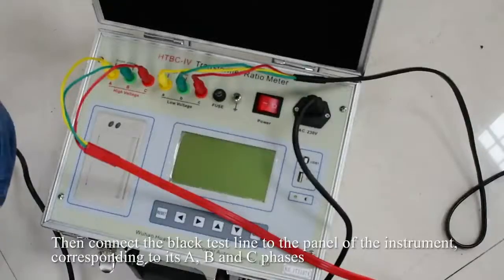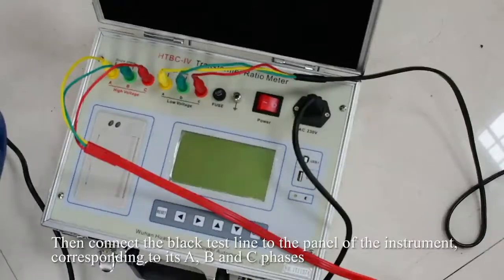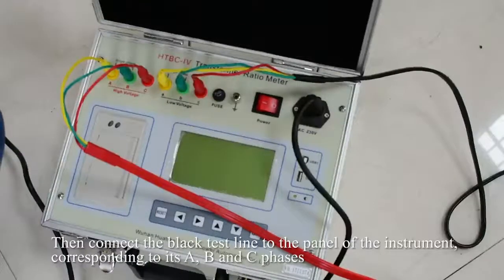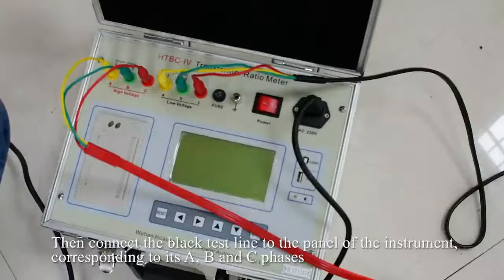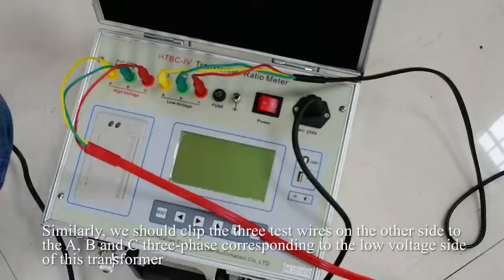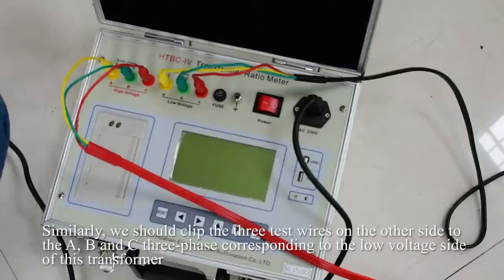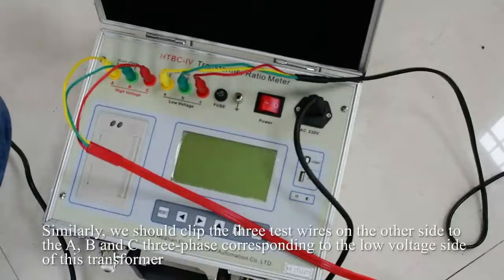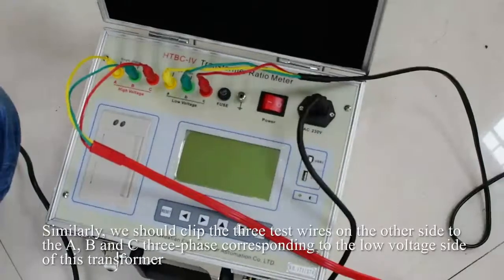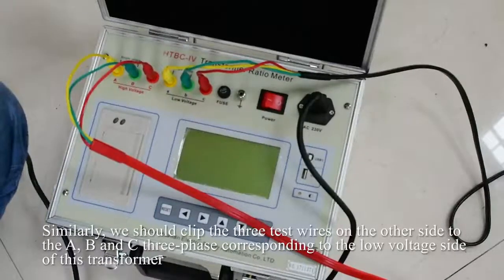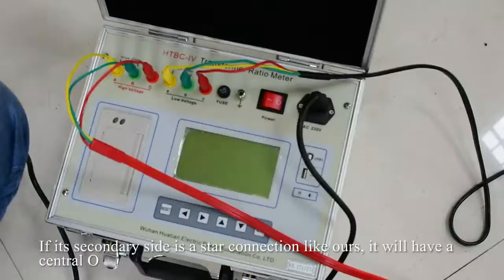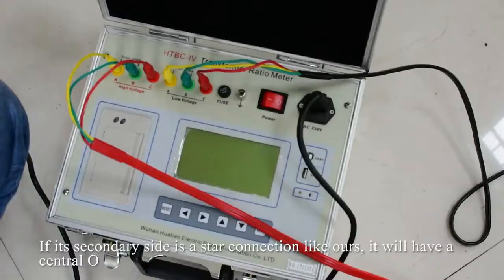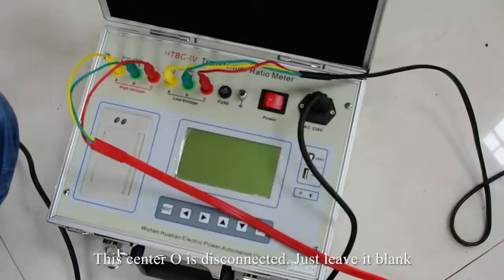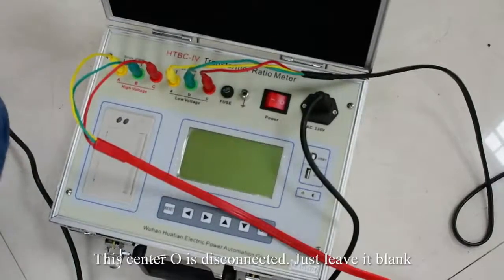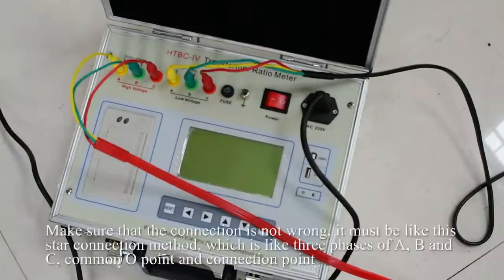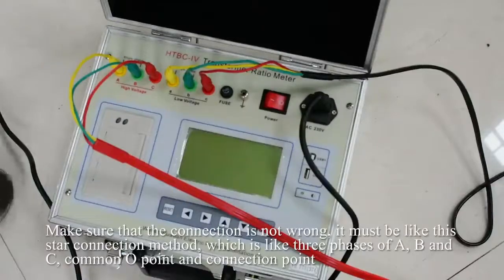Then connect the black test line to the panel of the instrument corresponding to its A, B, and C phases. Similarly, we should clip the three test wires on the other side to the A, B, and C three-phase terminals corresponding to the low voltage side of this transformer. If its secondary side is a star connection like ours, it will have a central zero. This center zero is disconnected. Just leave it blank. Make sure that the connection is not wrong.